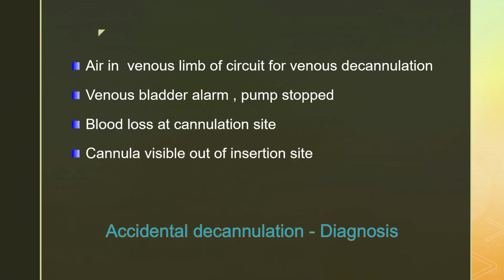Another drastic complication, like a blocked cannula, is accidental decannulation. One of the cannulas comes out. Again, the problem is worse, because once the cannula comes out, if it is a venous cannula, it will suck in air because of the negative pressure. The air fills the circuit, and you have to de-air the circuit entirely. The ECMO machine definitely stops. That is for sure.